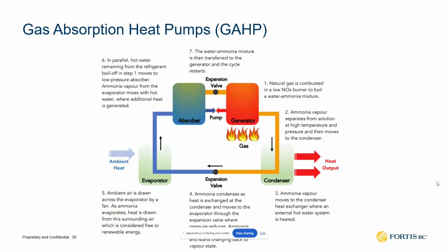Now let's talk about the gas absorption heat pump. For those of you not familiar with the gas absorption cycle, I'm going to give you a 10,000 feet high view of what it is. We have here a little schematic. You will recognize some components that are the same as the vapor compression cycle. On the vapor compression cycle, you will have a condenser, your expansion valve, and your evaporator. The difference starts when the refrigerant leaves the evaporator, and the refrigerant of choice for absorption heat pumps is ammonia.